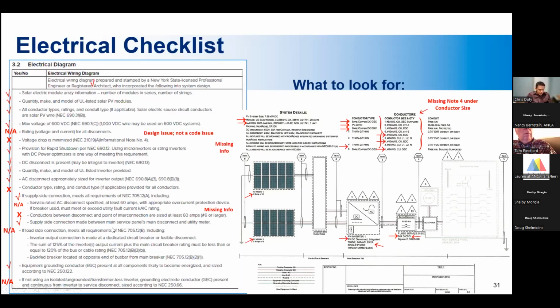And then this is an example of what it may look like when you're done. Some things may not be applicable, but you want to make sure that everything that is accounted for is checked off, and make a note of anything that's missing. And this will allow you, when you go on site to do the inspection, to just verify that the things that look good in the design are there and are installed correctly, and you can have more time to spend looking into missing information or design issues.